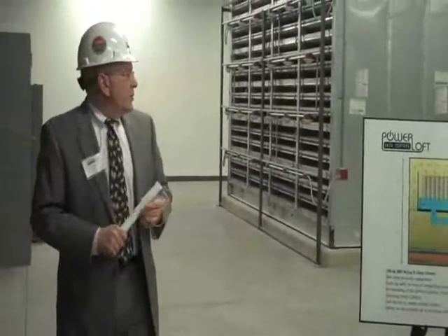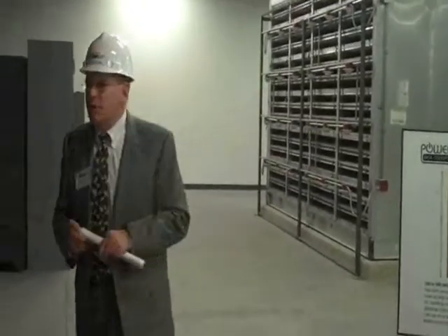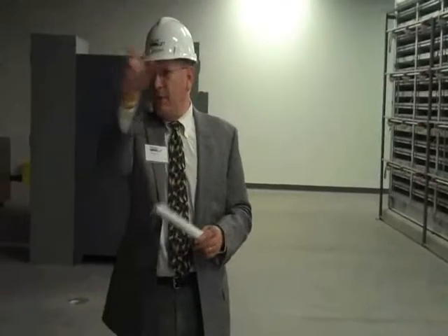You get fewer and fewer servers up there and fewer racks. So we've separated it into a two-story design. We're cooling from the first floor. These are large commercial air handling units. They're the largest ones that you can get that you can bring in three pieces over the road. That's why we have the overhead doors on the other side of this room.